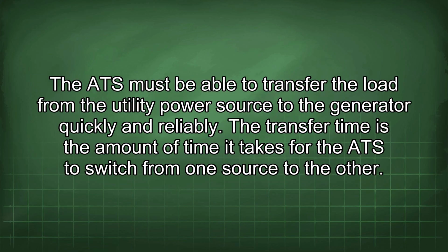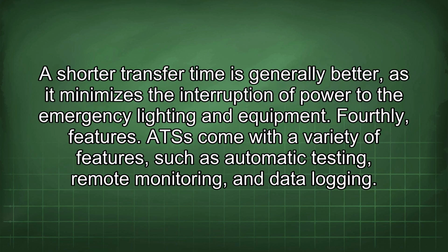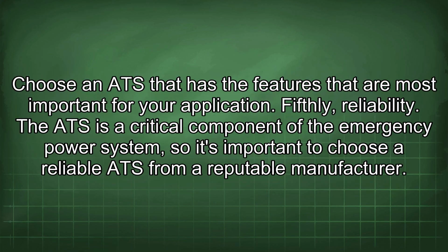Thirdly, transfer time. The ATS must be able to transfer the load from the utility power source to the generator quickly and reliably. The transfer time is the amount of time it takes for the ATS to switch from one source to the other. A shorter transfer time is generally better, as it minimizes the interruption of power to the emergency lighting and equipment. Fourthly, features. ATS come with a variety of features, such as automatic testing, remote monitoring, and data logging. Choose an ATS that has the features that are most important for your application. Fifthly, reliability. The ATS is a critical component of the emergency power system, so it's important to choose a reliable ATS from a reputable manufacturer.